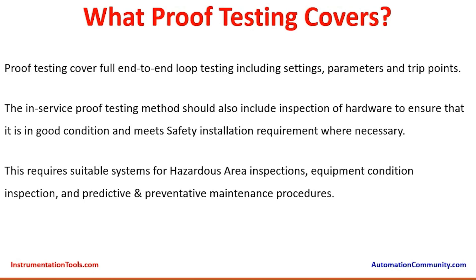Suppose a person goes for proof testing in future and sees a different value of the trip points between the document and the actual value available in the logic solver — they may get confused. So records also have to be maintained properly. Through proof testing, the maintenance person can ensure that the settings are done as per the design intent.